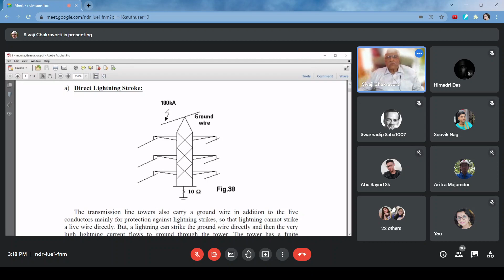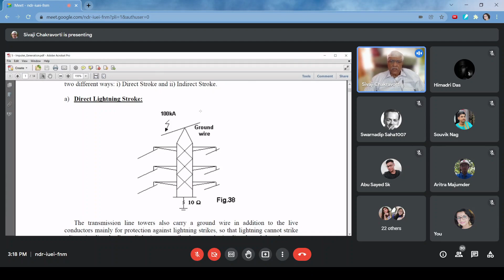If in future you have the good fortune of working somewhere, you will see that all these things which apparently look quite simple are not that simple. There are a lot of intricacies involved. So a direct lightning stroke will be protected against through the ground wire. And if any lightning somehow strikes the conductor, then forget about it. There will be a flashover. Nothing can be done about that. But why don't we consider that to be so important? Because the probability is significantly lower when we have the ground wire running on top.